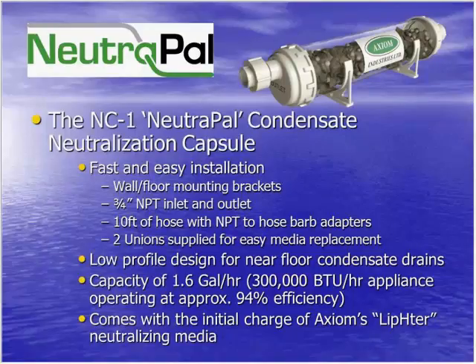So that's why we recommend changing it as part of the normal annual boiler maintenance, because more often than not, the media is not depleted. It's more the stuff that's getting caught in there that's clogging it up and coating it, from poor combustion or just debris from poor quality combustion air.